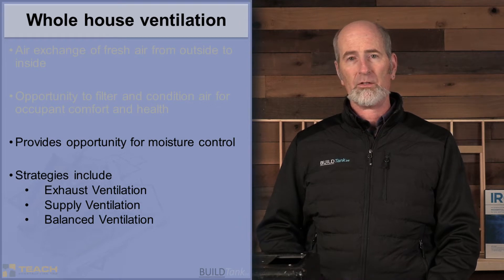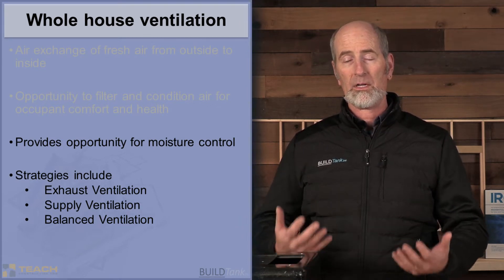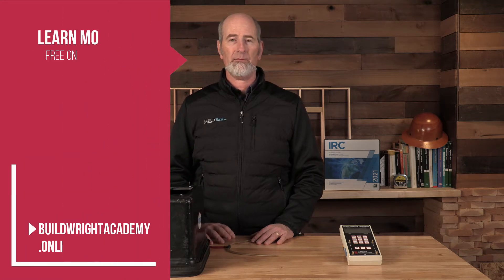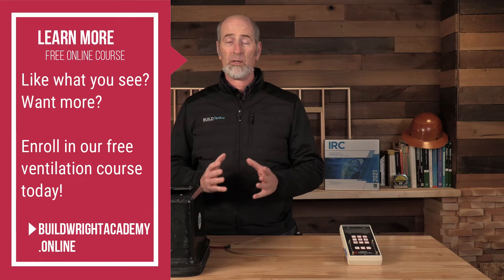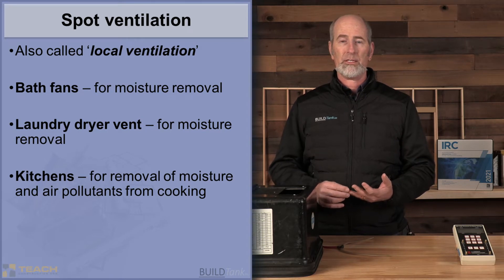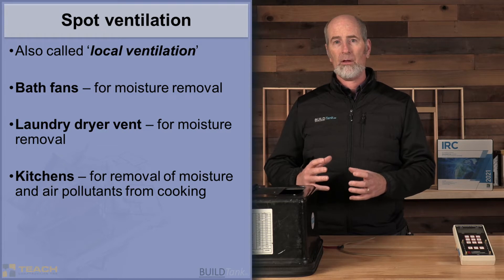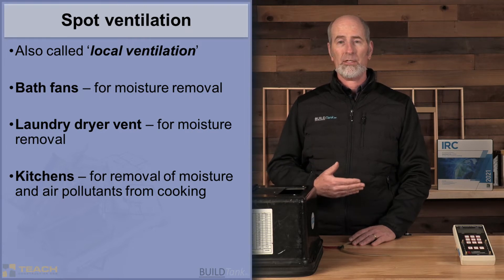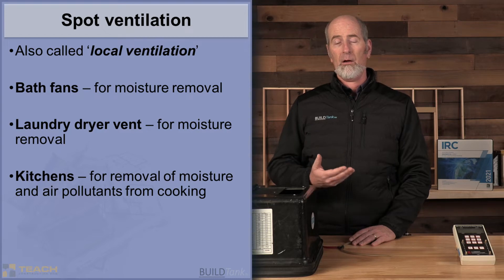When talking about the different strategies to ventilate a house in the whole house concept, you can use exhaust ventilation, supply ventilation, or balanced ventilation strategies. Regardless of which whole house controlled mechanical ventilation system you install, you also have to have spot ventilation systems. Spot ventilation is sometimes called local ventilation, and those are locations like bathrooms, laundries, and kitchens, where you're trying to remove pollutants from the house as soon as they're produced — primarily moisture in bathrooms and laundries, and cooking byproducts in kitchens.